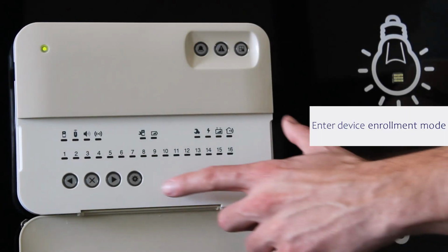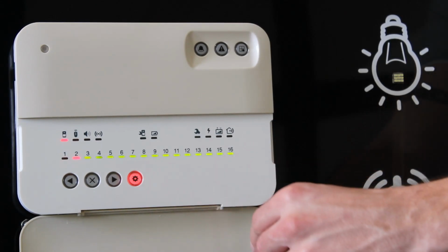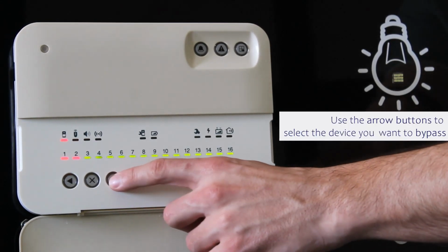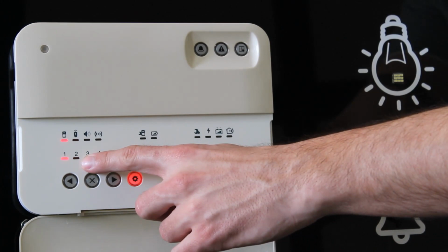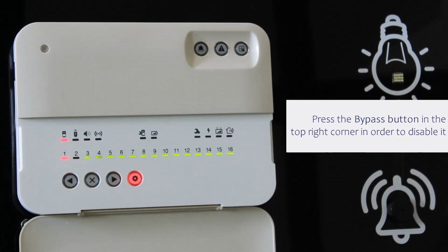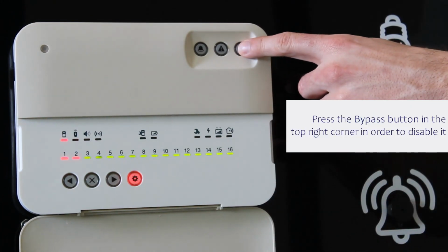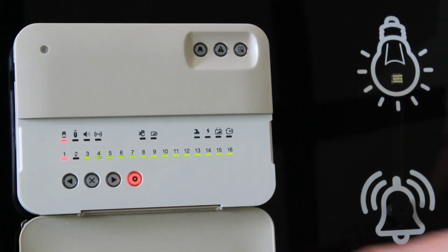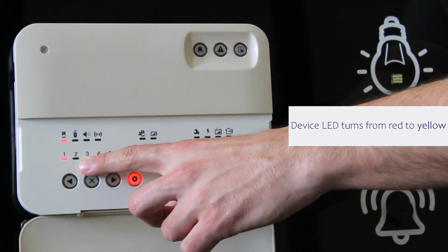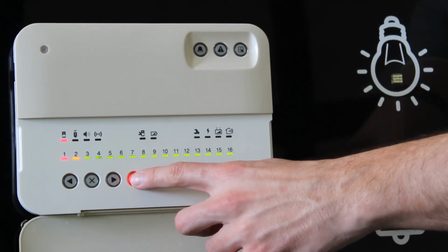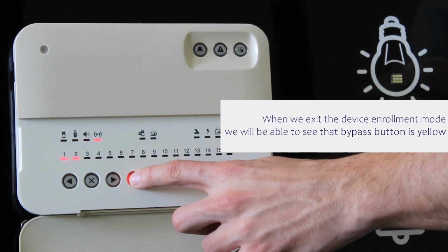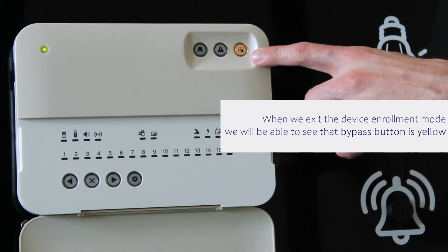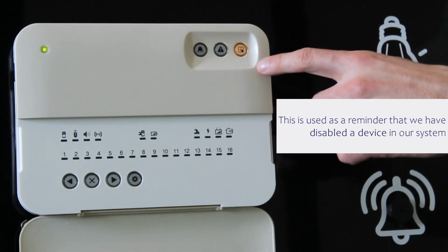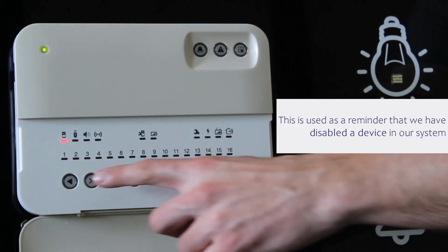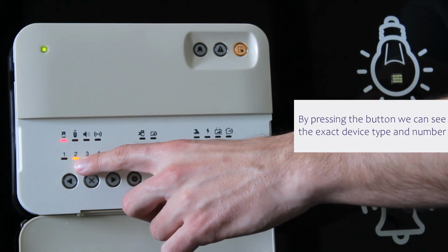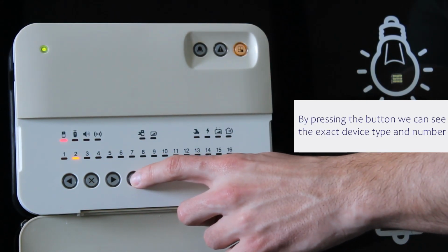We need to enter device enrollment mode, then by using the arrow buttons we can select the device we want to bypass. When we select the device, we can press the bypass button in the top right corner in order to disable it. As you can see, the device LED turns from red to yellow. When we exit the device enrollment mode, we will be able to see the bypass button is yellow, which is used as a reminder that we have disabled the device in our system. By pressing the button, we can see the exact device type and number.